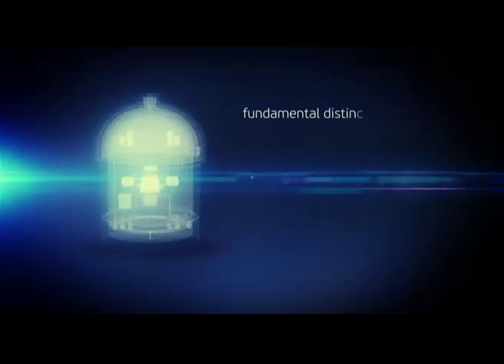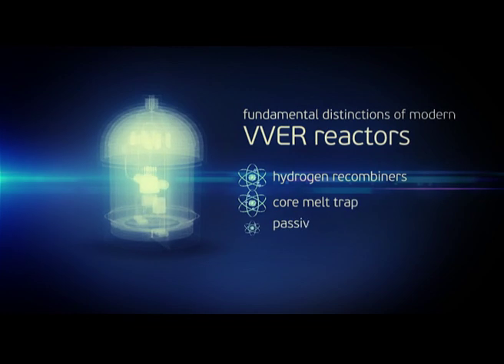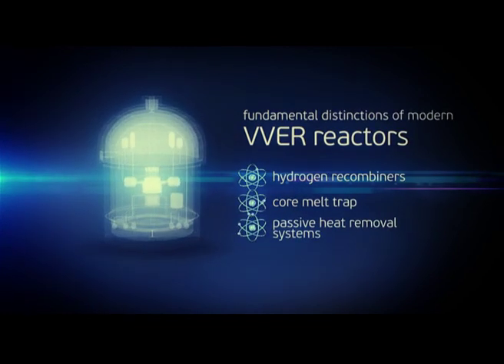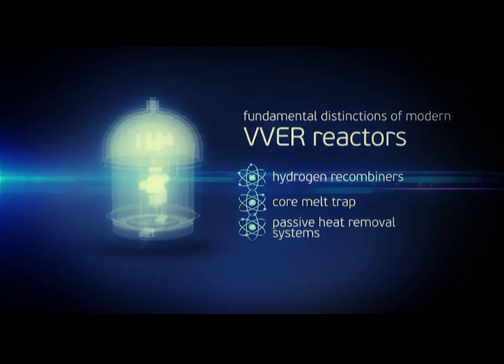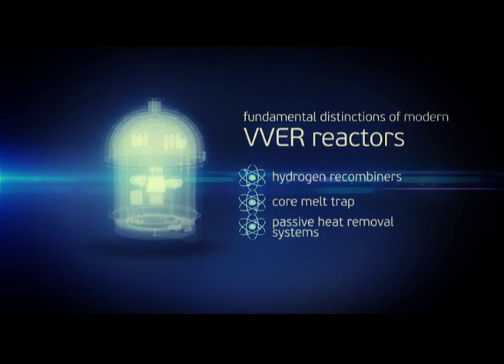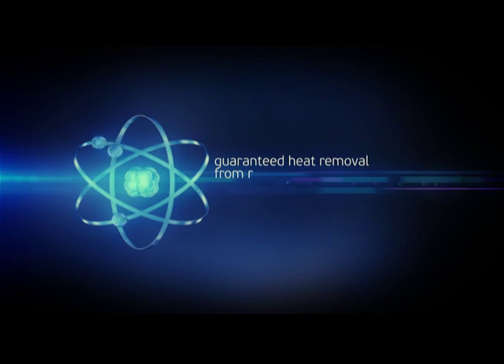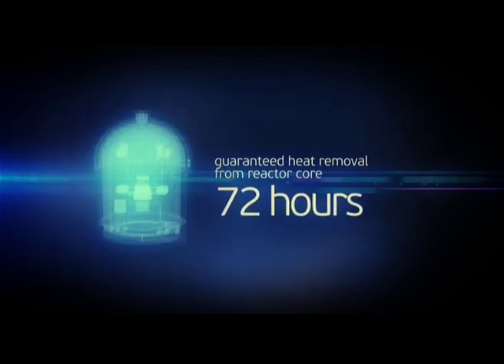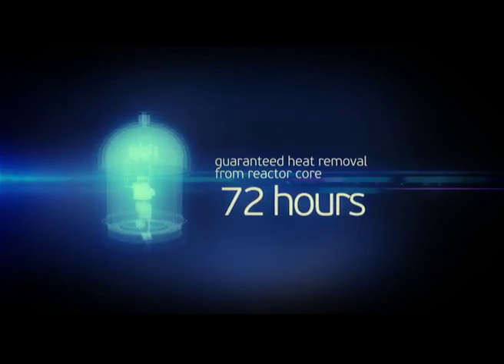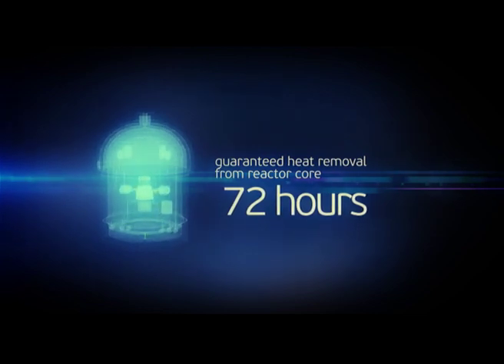Special engineering features such as hydrogen recombiners, core melt trap and passive heat removal systems are fundamental distinctions of modern VVER power units. The combination of active and passive safety systems allows maintaining guaranteed heat removal from the reactor core during 72 hours in case of a pipeline break. This time is sufficient to do required repairs.